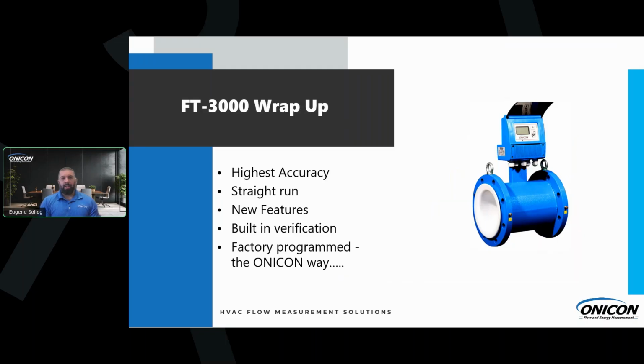All right, now to wrap this up for the FT3000 series, just some key points I wanted to re-highlight. This is the highest accuracy meter of anything that we offer, and we went into how that works. We're controlling that whole area. It's an extremely accurate and reliable flow meter, with the best straight run out of any flow meter that we offer, down to 0 straight run between two 90-degree elbows.